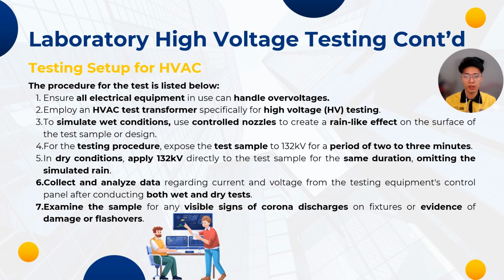The procedures for the test are listed in this slide. Firstly, we need to ensure that all the electrical equipment in use can handle the overvoltage. Second, we need to employ an HVAC test transformer specifically for high voltage testing. Moreover, in this project, we need to simulate wet condition, where a control nozzle is used to create a rain-like effect on the surface of the test sample. Whereas in the dry condition, the sample will be exposed to 132 kV for 2 to 3 minutes.